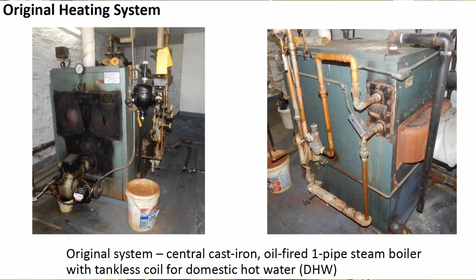But the problem with the boiler, of course, is that it burns fossil fuel and it's killing the planet. So we have to come up with some different kind of approach. The new system is an air source heat pump system, and in this case, because of what was available at the time, we went with what's called a multi-split system, which includes one outdoor unit. These are the outdoor units, ODUs, and then multiple indoor units inside each apartment.